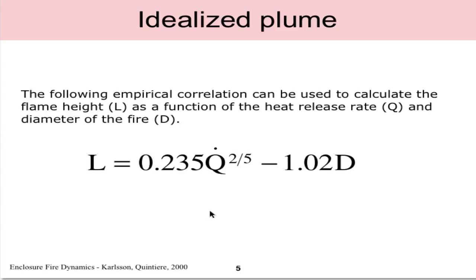In fact this equation from the textbook shows just that. It shows the L, the physical flame height, as a function of Q, the total heat release rate, and D, the diameter of the fire. Notice the units on this Q is in kilowatts and D is the diameter of the fire in meters or the equivalent diameter in meters.